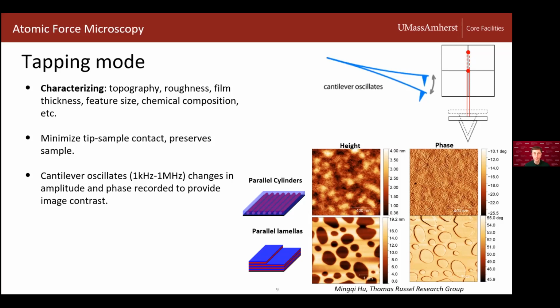And so what I'm showing here is from one of our users, Ming Chi. They have a two-phase system. This is a polymer block copolymer, and you can see here schematically that the blue region is one chemical composition, the red region is another. If we look at the height channel, we get an idea of the topography of our sample, but what's really powerful here is looking at the phase channel. Due to the differences of interaction between material 1 and material 2, the two different phases in this person's material system, we can get a better idea of chemical composition, some sort of phase distribution of the material within the sample.